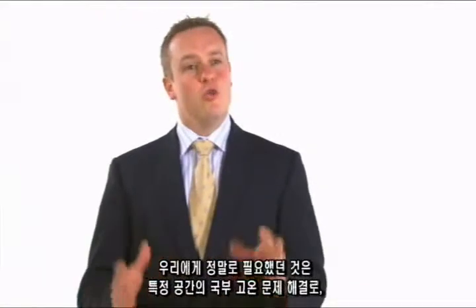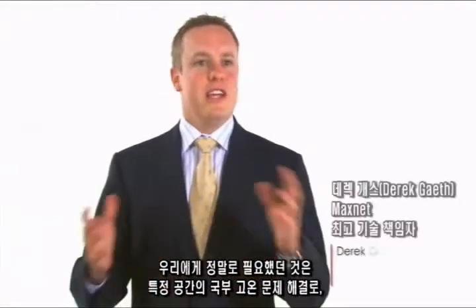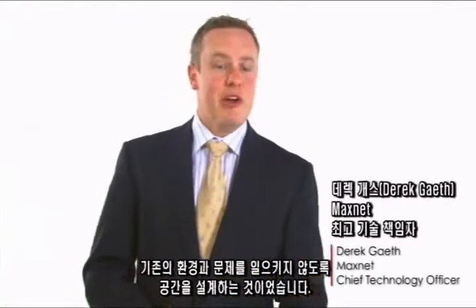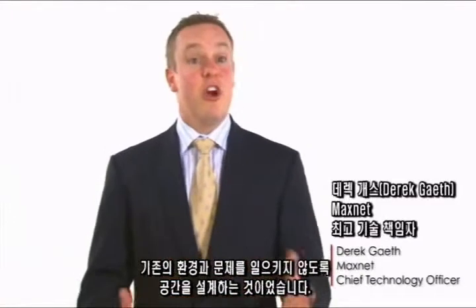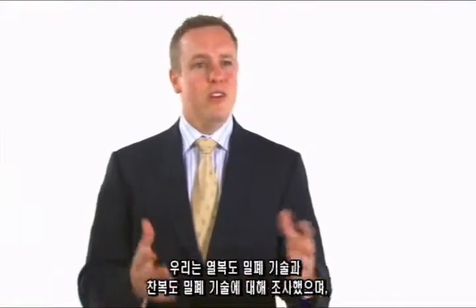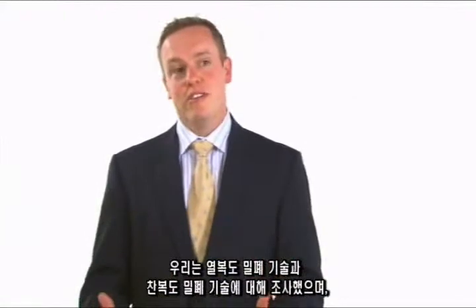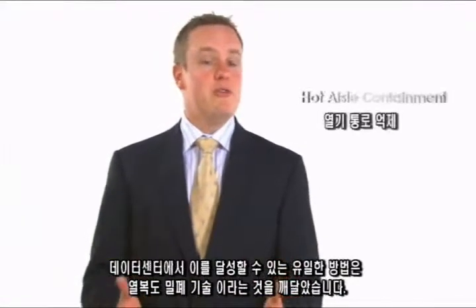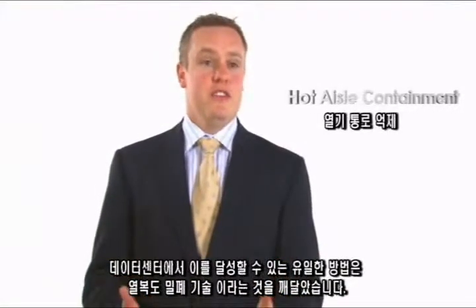We really needed a room neutral design that wasn't going to upset some of the tape libraries we had, some of the switches that couldn't cope with having a room heat up. Now, we looked at hot aisle containment, we looked at cold aisle containment, and realised that hot aisle containment was the only way that we were going to be able to achieve this in the data centre.